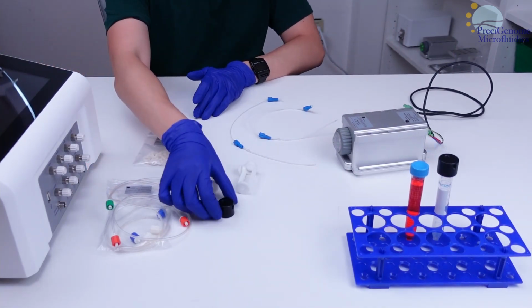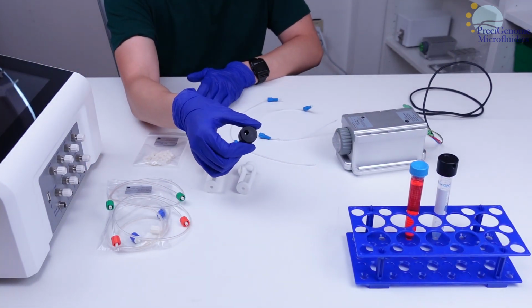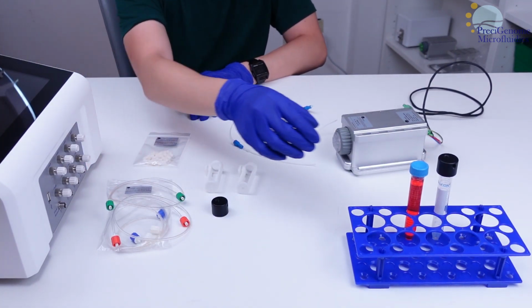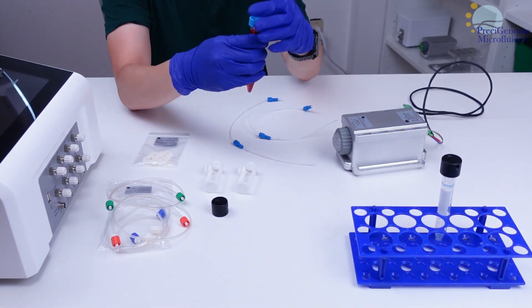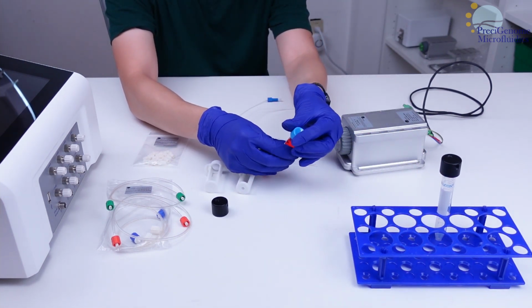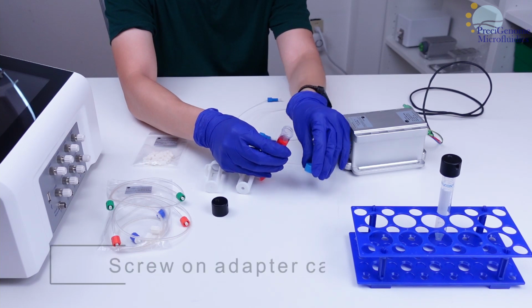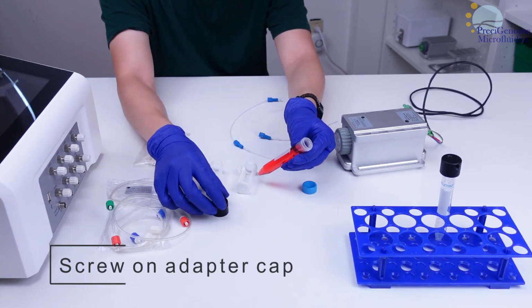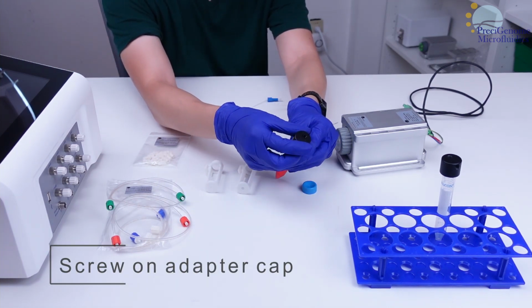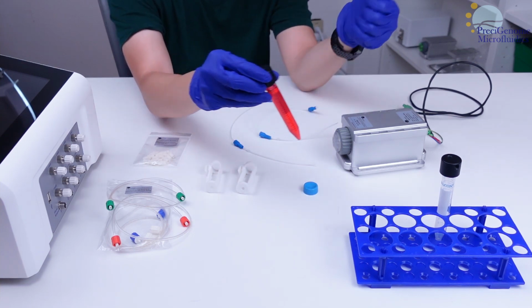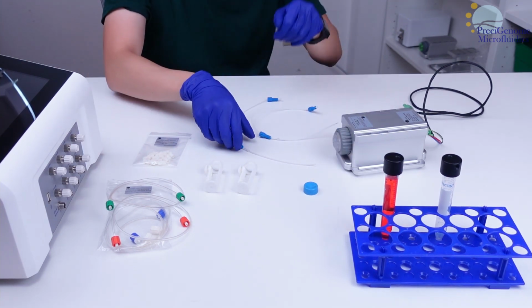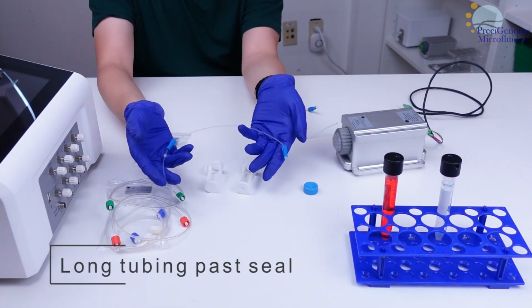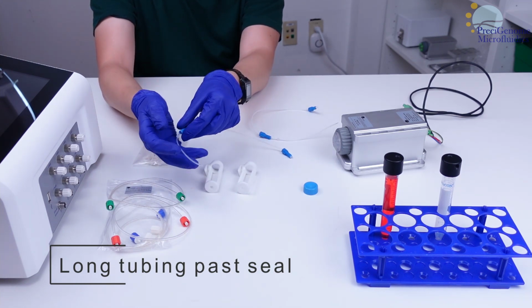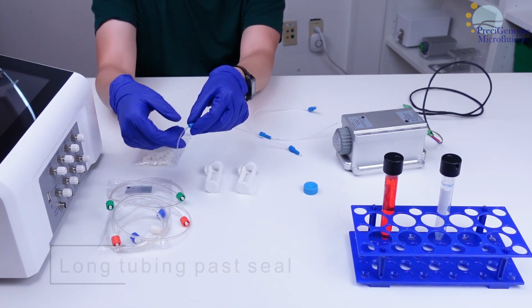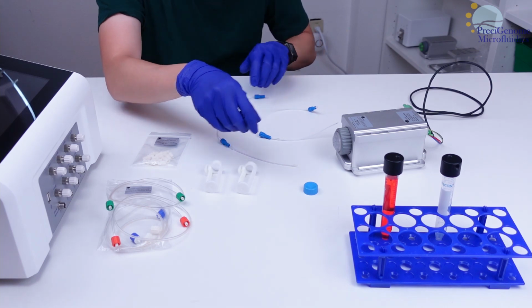Once you have prepared tubing for both reservoirs, it's time to integrate them into your setup. For a recirculation system, one of these should be filled with your desired fluid. Put the adapter cap on this reservoir. Now insert the PTFE tubing you've previously prepared. Leave a long section past the ferrule so it may protrude into the reservoir.